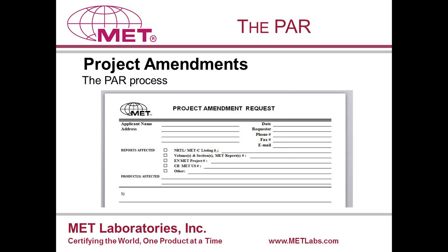The most important thing to remember about PARs is they must be dealt with before you make any changes. If an inspector shows up and finds a component in your product that is on the list as being safety critical, and it doesn't match what's in the product, you are possibly going to be prevented from labeling that product until the change has been assessed.